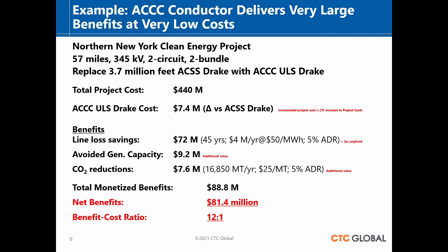But just the line loss savings alone were $4 million a year, less than a 2-year payback. And in New York, they say when doing these calculations, use 45 years and a 5% discount rate to give us what that net value is going to be. That's a $72 million value just on the line loss savings alone over the life of that unit.